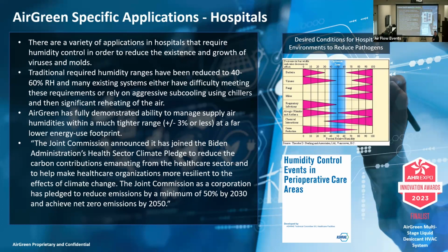And right now they do most of this work by brute force. Very low temperature, just hammer it and get the humidity down low, and then lots of reheat. Mm-hmm. So they're just hammering it, and it's not as energy efficient as it could be. If you're in Florida and you're running a hospital, why not have dehumidification built in for the outside air that you're bringing in, and then you can deal with it in a much more energy efficient way without changing a ton of infrastructure.